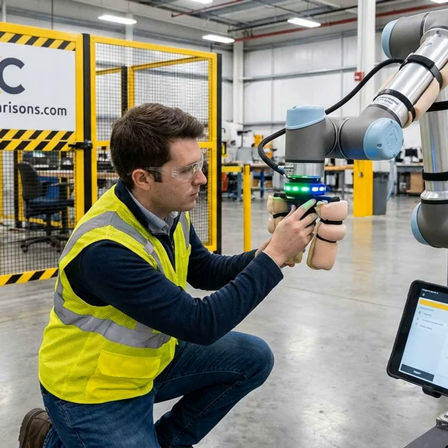Certification evidence hierarchy. When comparing vendors, look for evidence in this order: independent safety certificate, safety manual with exact model and software version, published PFH or PFHD value, defined stop category, defined performance level or SIL, documented safety input and output behavior, validated configuration limits. Only then marketing claims. Public examples include UR safety functions rated PLd category 3 with PFHD values below 1.8 times 10^-7 per hour. KUKA LBR iiwa safety functions rated PLd category 3 with functional safety up to SIL 2.